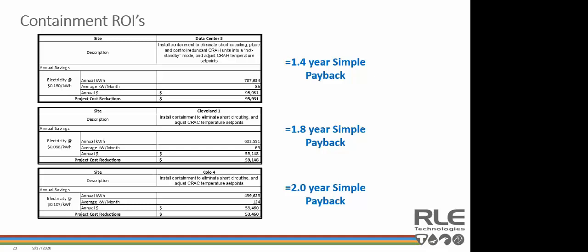And the same for the bottom. This was a co-location company that we had worked with. This is a smaller data center, so the savings aren't quite as large. They had done a lot of things right already, but they had not implemented any containment. And again, even with a fairly well-run, not too overcooled data center, we're able to show almost 500,000 kilowatt hours of savings a year. They were paying almost 11 cents a kilowatt hour, and we were able to show over a $53,000 a year savings. In this case, that worked out to right at a 2-year payback.